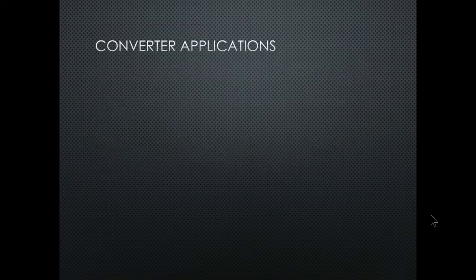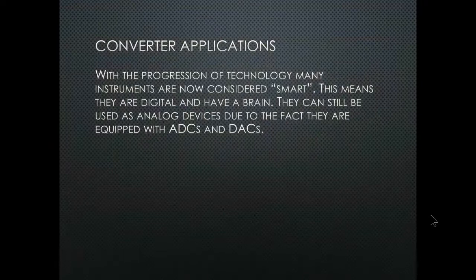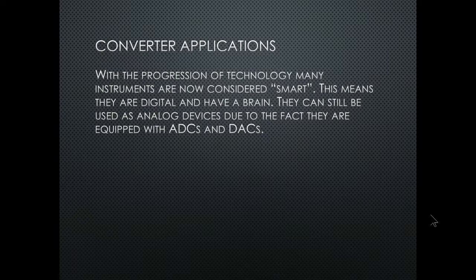The resolution — number of steps for the span — determines the accuracy. With higher resolution you have a higher accuracy. With the progression of technology, many instruments are now considered smart, meaning they are digital and have a brain. They can still be used as analog devices because they're equipped with ADCs and DACs. If you address a smart transmitter to zero, it becomes an analog transmitter.